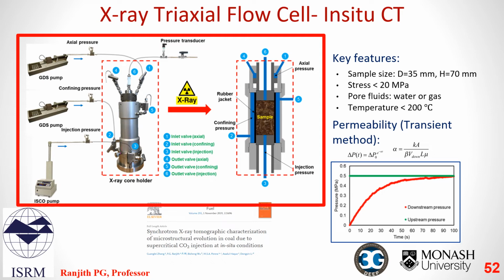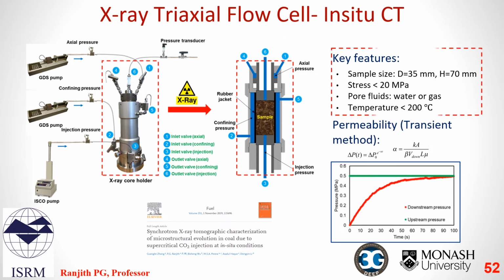This cell allows pore-scale imaging of fluid flow in porous rocks using X-ray microtomography combined with core flooding experiments. We can apply axial and confining stresses separately up to 20 MPa and inject water or gas into rocks for core flooding experiments. We can also wrap a heating jacket on the cell and heat up rock samples up to 200 degrees C. We can adapt the pressure transient method to measure the permeability of tight rocks to shorten the testing period.